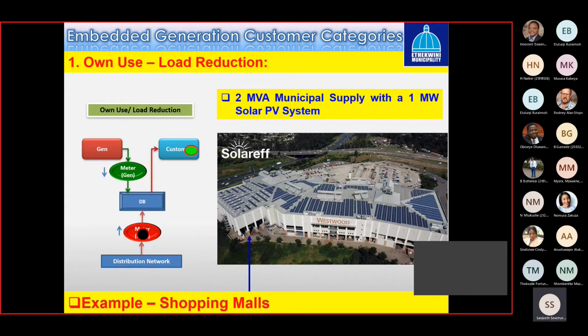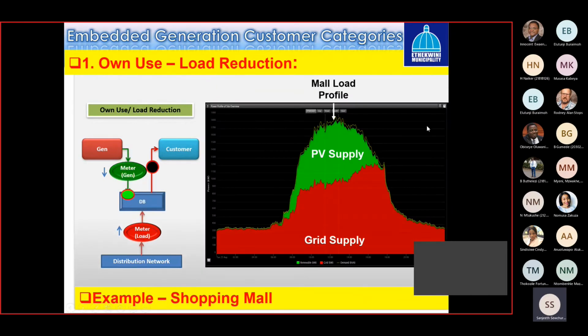So what is the reason for customers installing solar PV? The first reason is customers installing it for their own use. There's an example of a shopping center with a 2 megawatt or MVA municipal supply that installs a 1 megawatt PV system. Typically what happens is the PV will supply a portion of the customer's load during the day, and the rest of the electricity will be supplied from the grid. There is no excess energy that will be exported to the grid at any point in time.